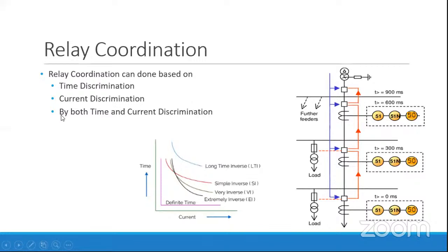Now the third one is by both time and current discrimination. We can say this is the best and ideal manner to provide relay coordination, so that it coordinates completely from the downstream to the upstream network. It gives reliability in case the fault current exceeds, as we can't predict how much fault current there will be if a certain fault persists in our feeder or in our network. So with this, we can provide protections based on time and current discrimination.